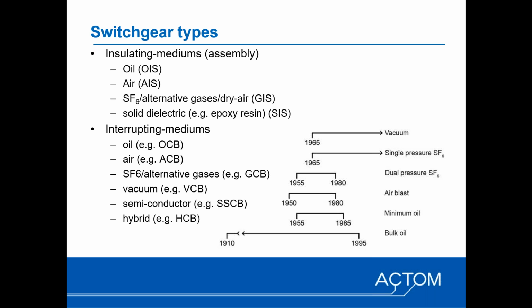And again, you've got oil, often referred to as an OCB or oil circuit breaker, air, SF6 or alternative gases, GCB, gas circuit breaker, of course, vacuum, which is very common and now the dominating interrupting medium within the medium voltage area, and that would often be called a VCB. But it's worth mentioning that you also get semiconductor switching devices, SSCBs, more common in low voltage and HVDC applications, and then hybrid, also for HVDC applications, or an HCB, which is a combination of a semiconductor switching device and a conventional mechanical switching device.